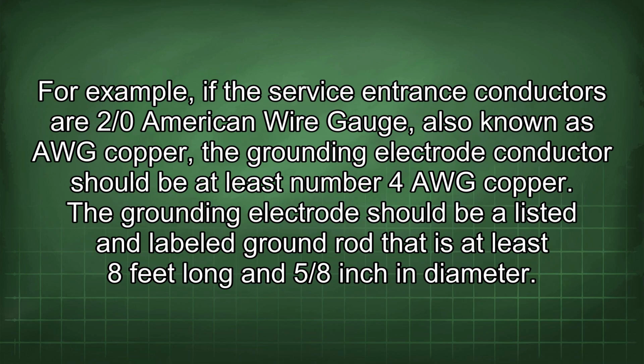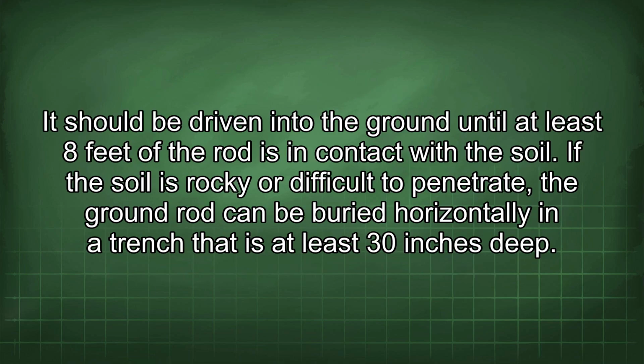For example, if the service entrance conductors are 2/0 American wire gauge, also known as AWG copper, the grounding electrode conductor should be at least number 4 AWG copper. The grounding electrode should be a listed and labeled ground rod that is at least 8 feet long and 5/8 inch in diameter. It should be driven into the ground until at least 8 feet of the rod is in contact with the soil.